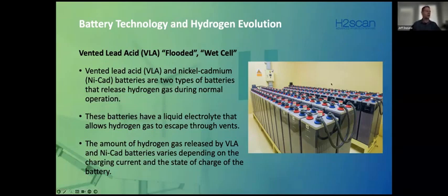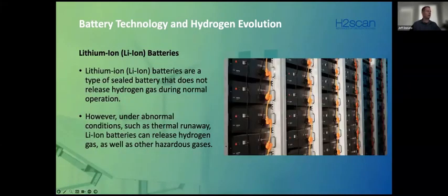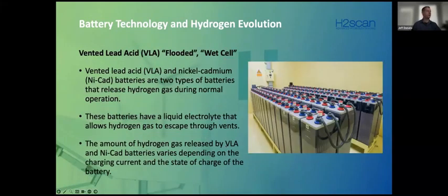In this case, we do have ventilation standards, which we'll talk about in a couple minutes, when it comes to properly ventilating hydrogen out of the battery area or the battery room. It really depends on the charge. I'm sorry, flip slides. It depends on the state of charge that the battery is in. On float voltage, there's a minimum amount of hydrogen being produced. If you're on boost or equalized charge, then you're going to produce more hydrogen.